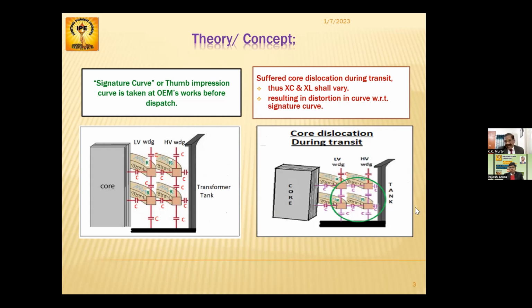Now, this figure is of distortion during transportation. The transformer nowadays is transported on a multi-wheeled, low-bedded trailer, known as a tractor trailer. So if it gets a jerk or shock during transportation, the capacitance and the inductance will change with respect to each other as well as with respect to the core. This figure shows the core distortion during transportation. Thus, XL and XC shall vary, resulting in distortion in the curve with respect to the signature curve.